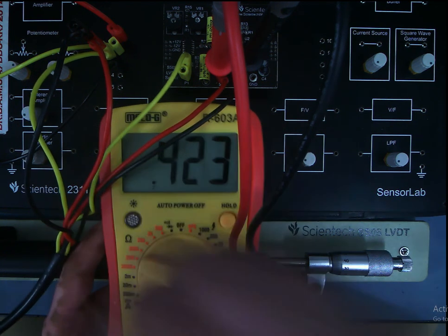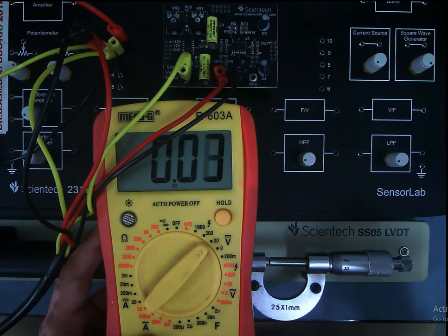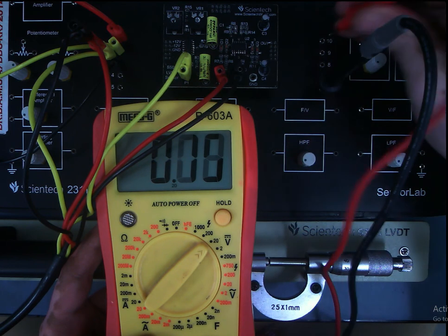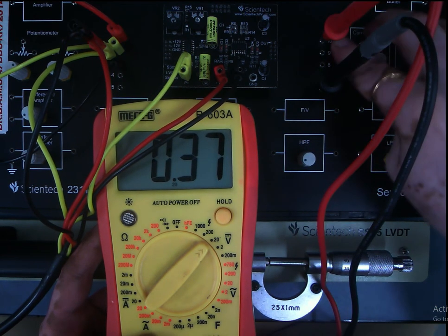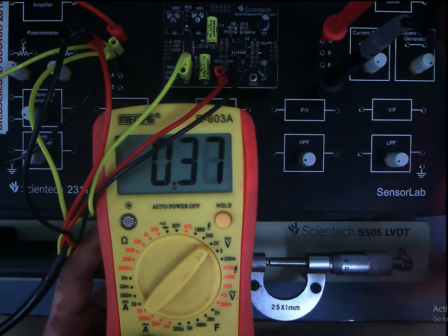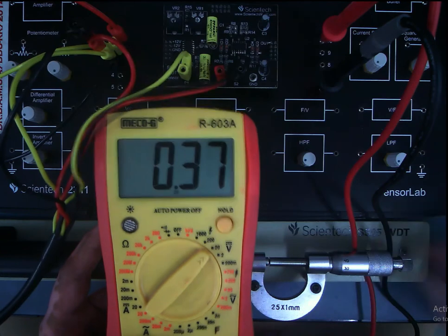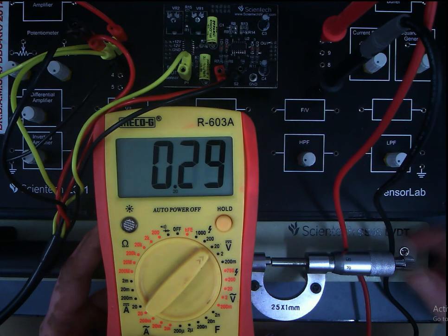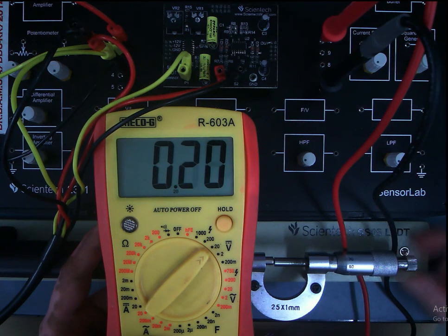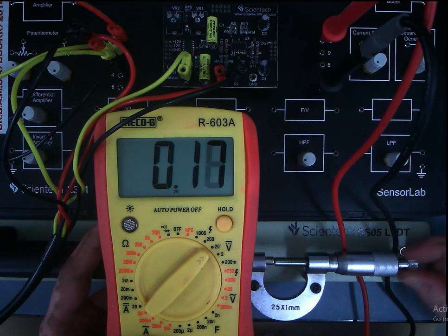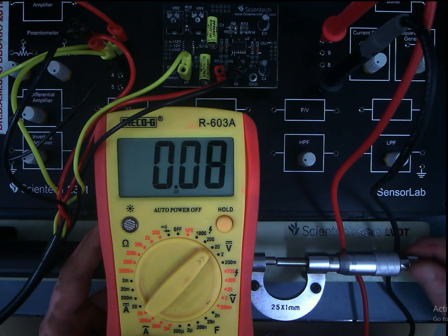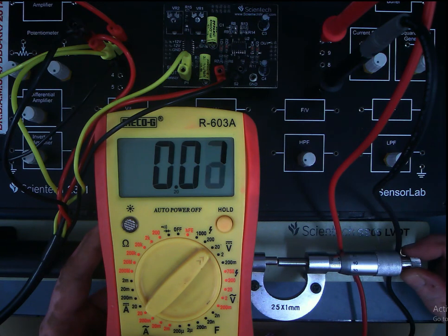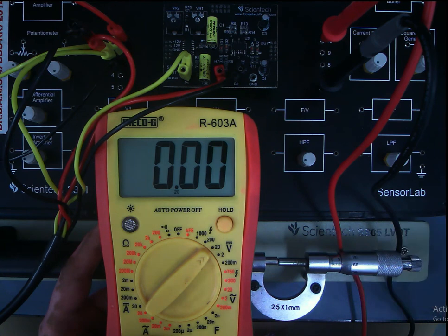Alright. Now I am more interested in the DC part. So I will go to this DC value and I will be measuring the voltage across two secondaries. So output is available across this terminal 10 and terminal 6. So now we will be looking a bit at the values so that we can have a 0 and then positive and negative extremes. So you see here I am taking the core towards right. So the core is coming out from the cavity of this winding. So you see here, now you can see it is a DC voltage. So this becomes 0. All right.